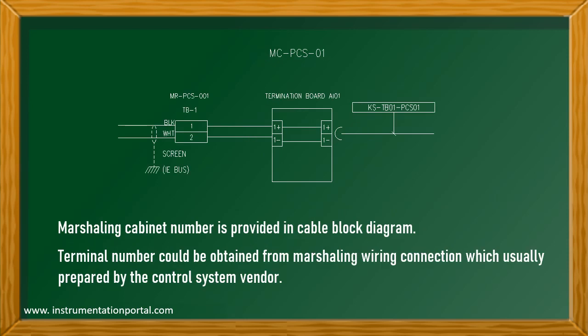This is the marshaling cabinet section. Marshaling cabinet number is provided in cable block diagram. Terminal number could be obtained from marshaling wiring connection, which is usually prepared by the control system vendor. In addition, if termination board or field terminal assembly is used, the information also shall come from control system vendor.